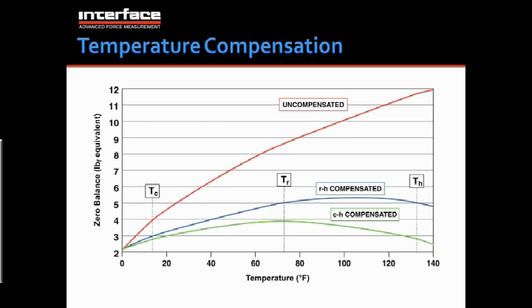What we do in order to compensate is we balance this bridge in order to minimize those errors. We add wire to either the left or the right legs of the bridge in order to keep that amount of error as minimal as possible. There will always be some amount of error, but we'll always try to keep that to the minimum possible.